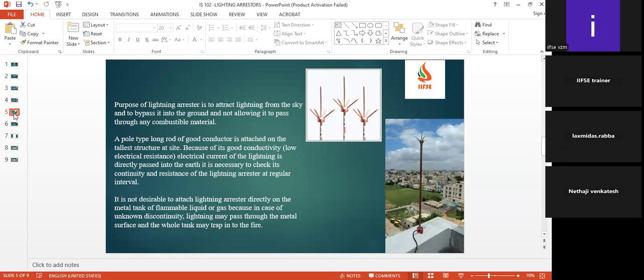Again, it is not desirable to attach a lightning arrestor directly on a metallic tank or any flammable liquid or gas, because in case of any unknown discontinuity, the lightning may pass through the metal surface and the whole tank may catch fire. So that's why we should have a separate path for taking this lightning energy to the ground.